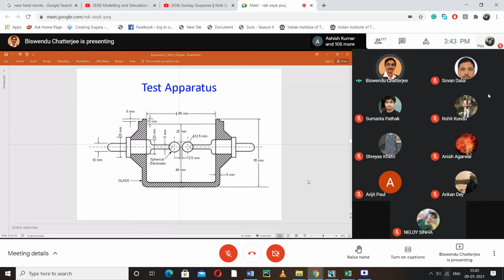It is a glass apparatus. Please remember, this is a glass apparatus with two electrodes fixed inside the glass and has a specific dimension. See, the oil is subjected between two sphere gaps spaced by 2.5 millimeter, and the diameter is 12.5 millimeter, and all the distances are fixed. Whether you test here or test in Kanyakumari, you will have to test in a specific apparatus so that the result is valid throughout India, in fact throughout the world. So with this, you will start the experiment.